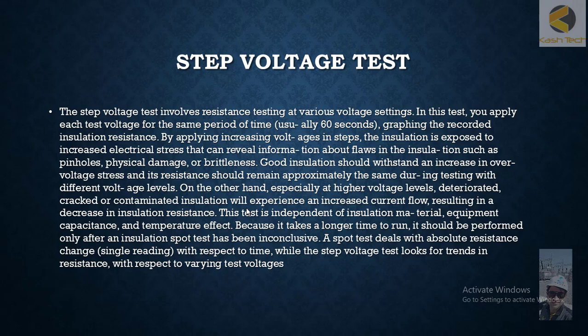This test is independent of insulation material, equipment capacitance, and temperature effect. Because it takes a longer time to run, it should be performed only after the insulation spot test has been inconclusive.